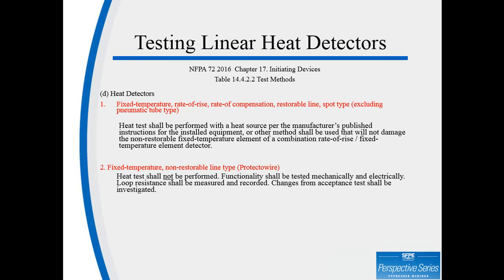You only functionally test it by shorting it out at the end of the loop to make sure it goes into alarm, and you record the resistance to make sure it's not appreciably different from the acceptance test.